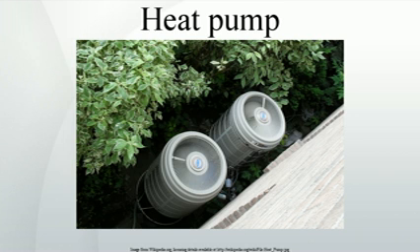The working fluid, in its gaseous state, is pressurized and circulated through the system by a compressor. On the discharge side of the compressor, the now hot and highly pressurized vapor is cooled in a heat exchanger, called a condenser, until it condenses into a high-pressure, moderate-temperature liquid. The condensed refrigerant then passes through a pressure-lowering device, also called a metering device. This may be an expansion valve, capillary tube, or possibly a work-extracting device such as a turbine.